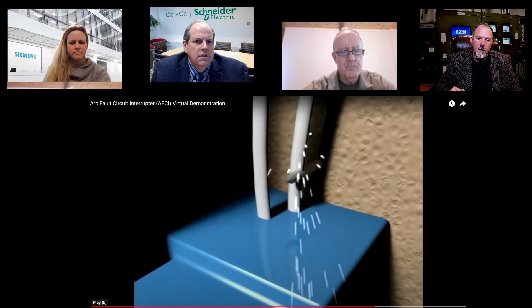While we're talking about this, I want to show this, if I can. This shows a staple, and this is to your point, Keith. You have a staple on a conductor, which could be behind the wall. In this case it looks like it's in an attic or whatnot. But that staple was driven in too hard, and you can just barely see it. He turned the lights off, probably filming this with a flip phone based on the image. But you can see how it's just sitting there, and there's nothing in the immediate area around it. Now he's going to turn the light back on again.